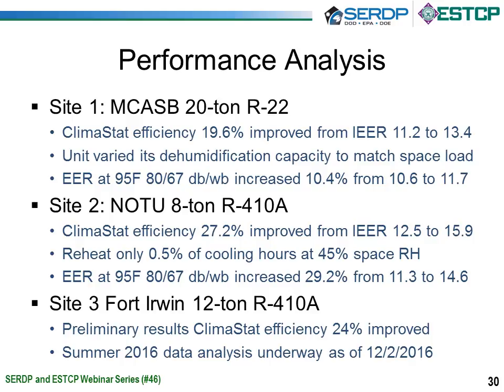Some key findings from Site 1. The ClimaStat efficiency, which would be the second summer versus the first summer, improved from 11.2 to 13.4. The unit varied its dehumidification capacity to match the space load, meaning in more humid conditions it would provide more dehumidification and keep the humidity below 60%. And during drier times of the year, it reduced the dehumidification capacity, allowing the humidity to float upwards into the 50% area and improving the energy efficiency, or reducing the amount of energy consumption of the unit.